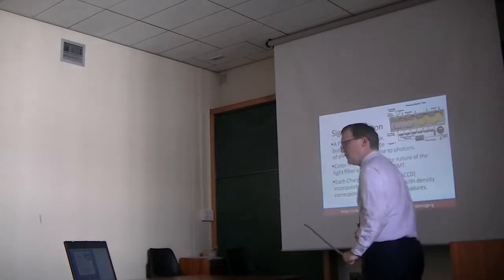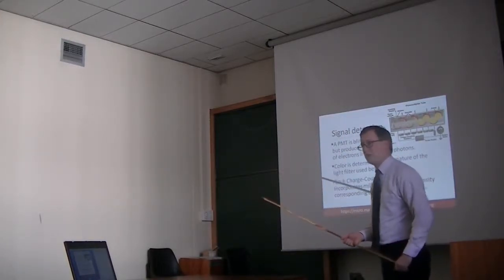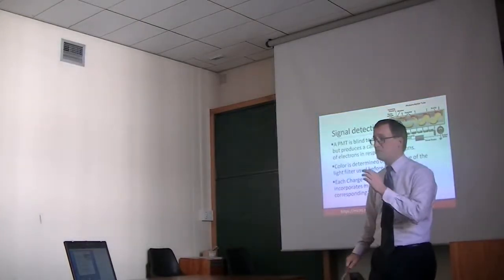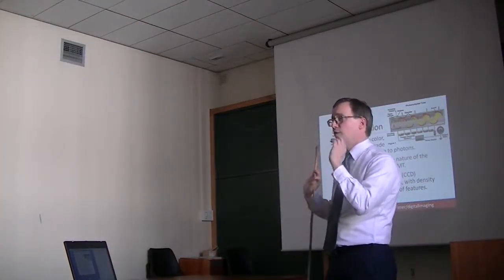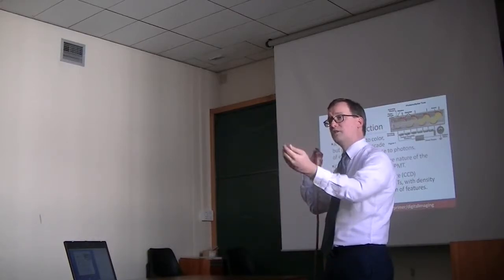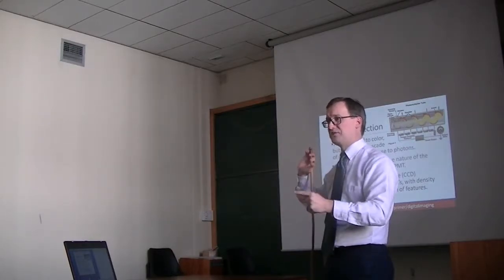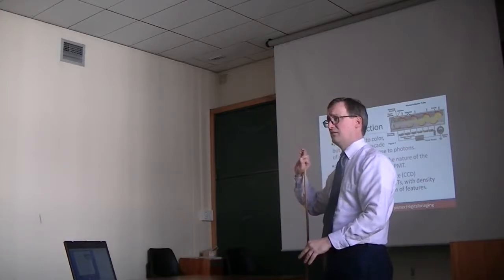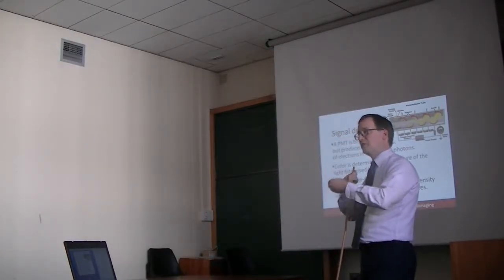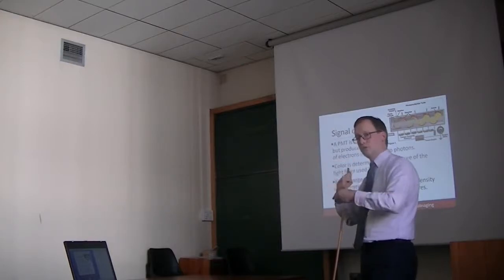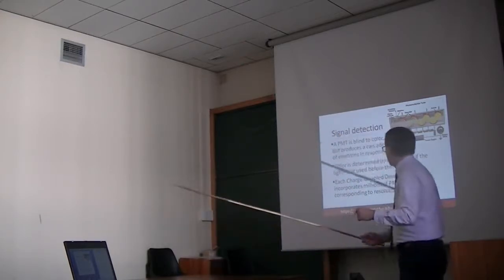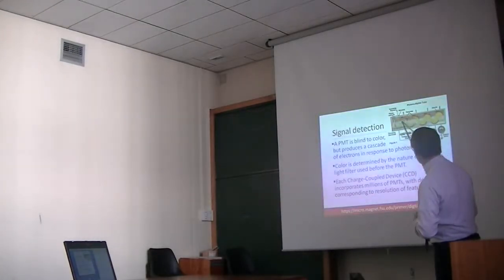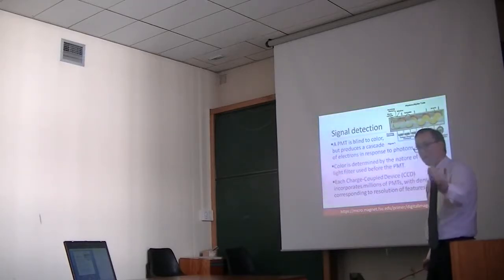In a photomultiplier, the device is blind to color — these things are monochromatic. Any photon that arrives is received and amplified into an electrical signal: receipt of the photon causes a cascade of electrons. It's very like an electron multiplier, but instead of an ion arriving, we have a photon kicking off that cascade. We've got a photocathode that produces the initial stream of electrons and dynodes that in turn amplify that signal.